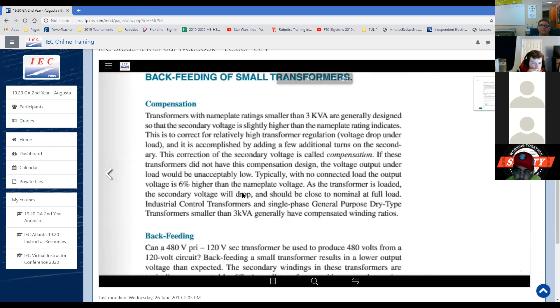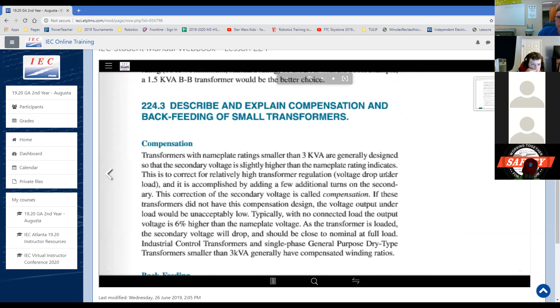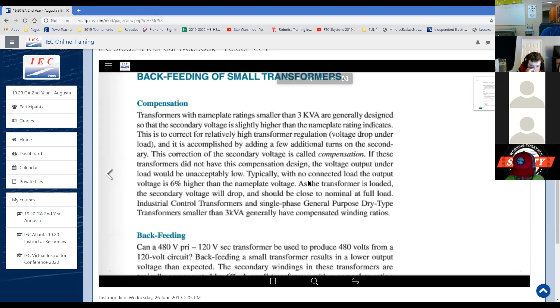What's compensation? Transformers with nameplate ratings smaller than 3 kVA are generally designed so that the secondary voltage is slightly higher than the nameplate with no connected load. Typically, with no connected load, the output voltage is 6% higher than the nameplate. So, what does that mean?